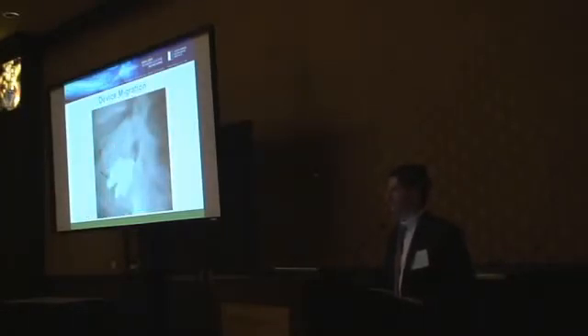Well, then you may remember this one. This is a patient with new onset low back pain approximately 4 months after implantation of the ProDisc, and shows the anterior migration of the superior end plate over the inferior end plate. It was thought to be a result of the separation of the polyethylene inlay from the inferior end plate. So there's a polyethylene core here that clicks into the metal end plate here, and it was thought that it popped out and dislocated basically.